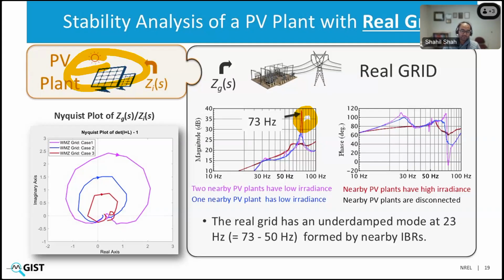If we have only one PV plant with low irradiance in proximity, the impedance response of the grid changes to blue, which has a resonance mode at 73 Hertz, but it is more damped. And for when these PV plants in proximity have high irradiance, or when they are not connected, we see these black or red traces, which don't have this resonance mode. So when you use just the short circuit ratio, you are assuming that the grid impedance is inductive. It is just flat like a line. But these other IBRs in the region are creating this high impedance or resonance mode at 73 Hertz, which in the rotating reference frame becomes 23 Hertz.